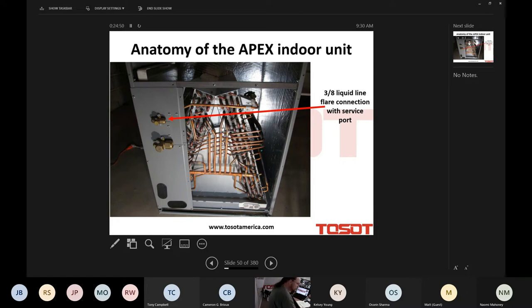Here's maybe feature number one of the day. Something I really, really love about this product. We have service valves. There's a 3/8 inch liquid. There's a 3/4 inch gas. But if you look closely at those valves, guys, of the indoor unit, and remember, we're still on the indoor unit, you'll notice that there's service valves on each. That's a beautiful thing. Nobody does that. And I love that Tosot does that with this product. You may not be able to appreciate it, but I can.